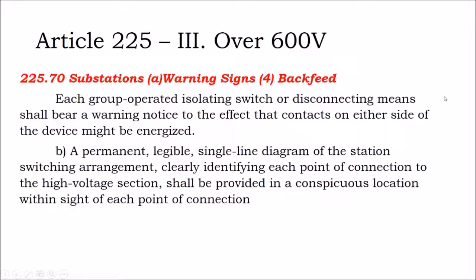Let's see. So substations have a warning sign that says each group-operated isolating switch or disconnecting means shall bear a warning notice to the effect that contacts on either side of the device might be energized. A permanent, legible, single line diagram of the station switching arrangement, clearly identifying each point of connection to the high voltage section, shall be provided in a conspicuous location within sight of each point of connection. So on a substation, wherever you connect to high voltage, you have to provide a permanent placard of a single line diagram showing that switching arrangement.